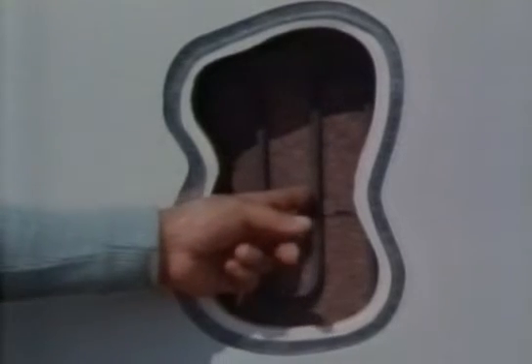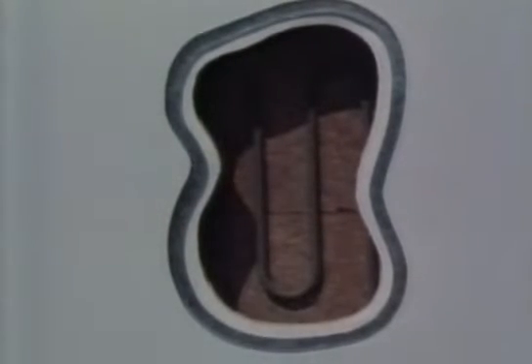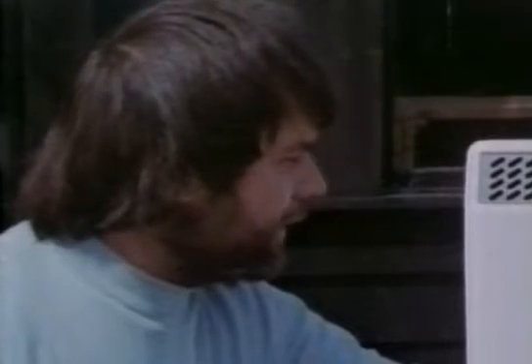The most common sort of electric central heating doesn't use boilers at all. By placing this hot brick in the cold water, you can see the energy stored in the brick. This is basically the principle behind electric night storage radiators. And this particular radiator we've cut away so you can actually see the element, and at night the element heats up and transfers its energy into the bricks, and they charge up very, very hot indeed, and the following day they can give out the stored heat throughout the on-peak period when electricity is a lot more expensive.